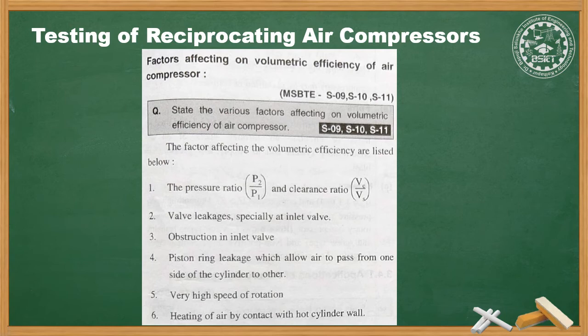If the compressor is not maintained properly, the volumetric efficiency will decrease. The general volumetric efficiency varies from 70 to 85% according to the type of compressor.